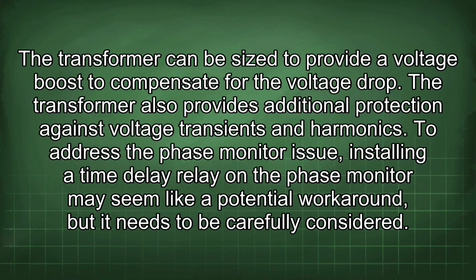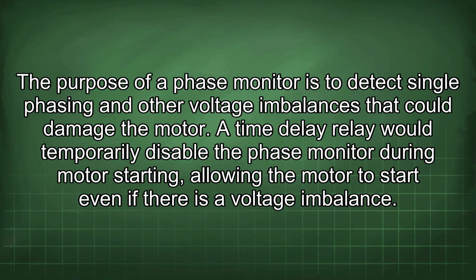To address the phase monitor issue, installing a time delay relay on the phase monitor may seem like a potential workaround, but it needs to be carefully considered. The purpose of a phase monitor is to detect single phasing and other voltage imbalances that could damage the motor. A time delay relay would temporarily disable the phase monitor during motor starting, allowing the motor to start even if there is a voltage imbalance.